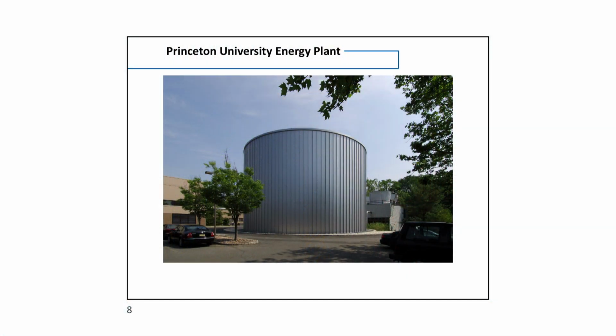Here's our thermal storage tank, 80 feet in diameter, 50 feet above grade and another 20 feet below grade. This is such a good deal. It's probably the best return on investment that I've ever made in terms of a project I've done. 3-4 year payback. There's not many businesses that can't tolerate that.